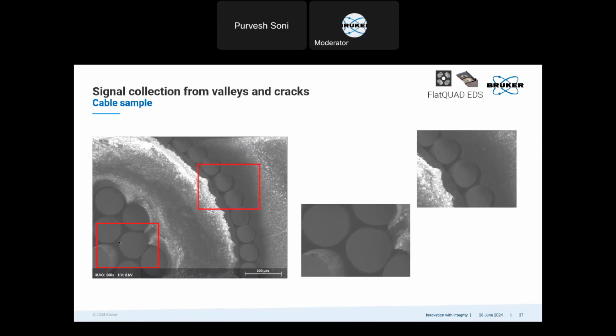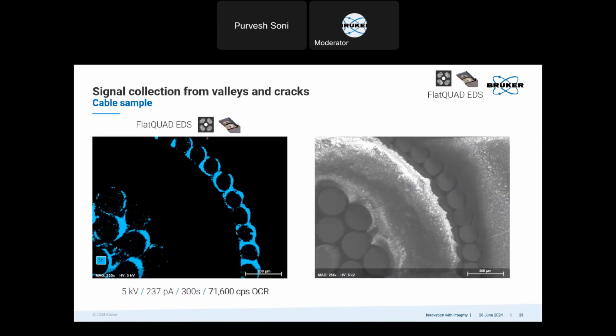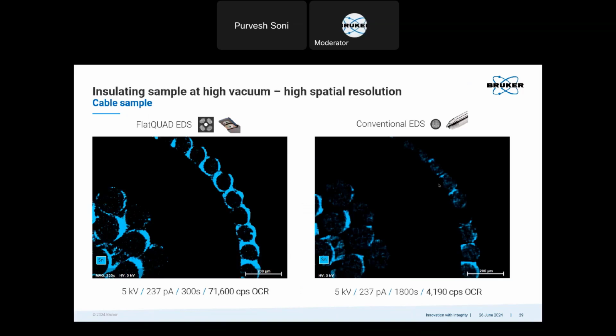And you see that there are some cracks and crevices and valleys in this material, so if you zoom into this, then you can see. With the FlatQuAD, because of the annular four-segment design, we could measure around this layer, and also in the valleys. And if we compare this with a conventional detector, then we can see that there's a strong data loss from around these copper wires where tin is coated. So this is what you gain when you have a four-segment detector and you are measuring very close to the sample. That data loss is very low because of shadowing or topography. And also because of the high count rate for this measurement, I only had to measure for 5 minutes, but because of the low count rate of a conventional detector, I had to measure for 30 minutes.